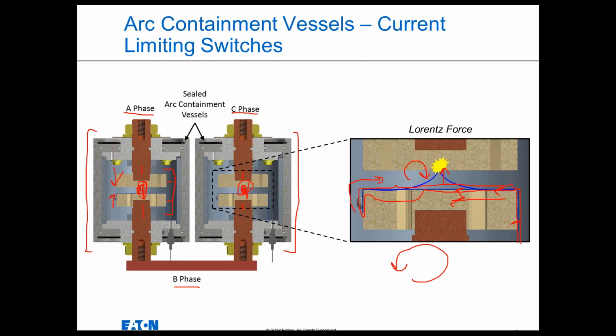Essentially what we've done is create a path of lower impedance for that arcing fault energy to flow, so that it immediately extinguishes itself in that unintended location.